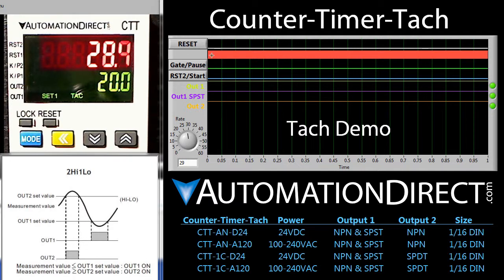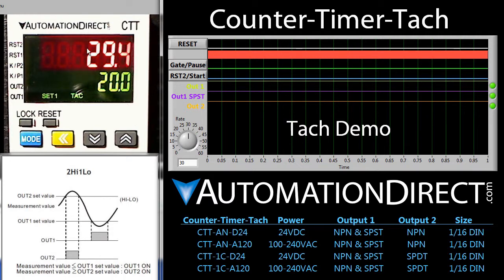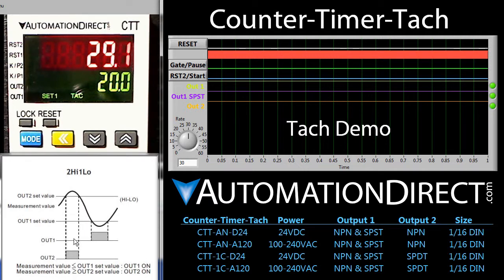Our TAC signal is shown here. It's toggling too fast for our display resolution, but you can see the rate that we dialed in here – I'm going to change that to 30 – and you can see the result on the screen here. We have the TAC set up in a 2-high 1-low output mode – that is, output 2 will be active if the signal gets above our high set point and output 1 will become active if the signal goes below our lower set value – hence the name 2-high 1-low.